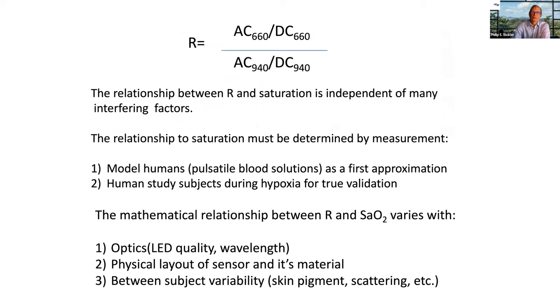So all pulse oximeters work on this ratio. And the nice thing about this ratio is it's dimensionless, and it's independent of a lot of the confounding factors that can interfere with pulse oximetry. For example, it's in theory independent of the size of the individual's finger, and it also, theoretically at least, should be independent of the subject's skin pigmentation. So this is a method that theoretically should be immune to a lot of the interfering problems with other methods of non-invasive oxygen saturation that had preceded it.